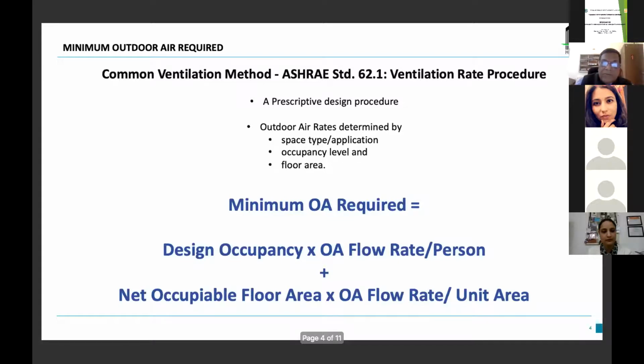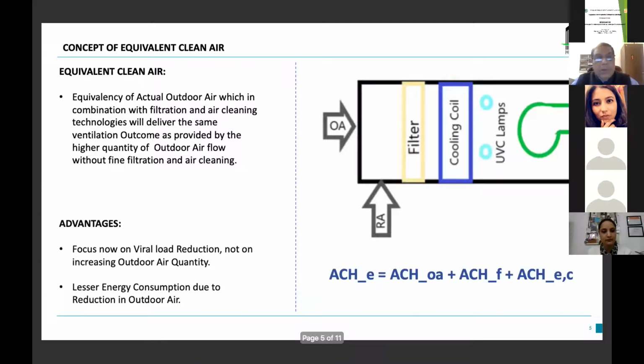If you can see the formula on the screen, it depends on design occupancy, the outdoor air flow rate per person as specified in the ASHRAE standard, net occupiable floor area, and outdoor air flow rate per unit area. The logic behind this is that you require minimum outdoor air to compensate for the fresh breathing air required by the occupants in the space. And the second element is the pollutant contaminants generated by the building interiors. But situations like this COVID-19 viral load have not been considered so seriously.